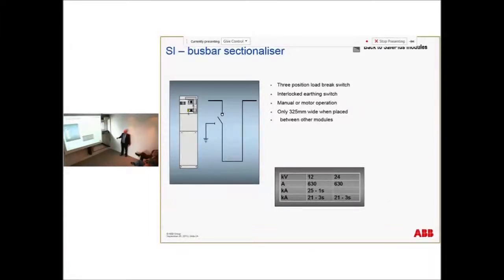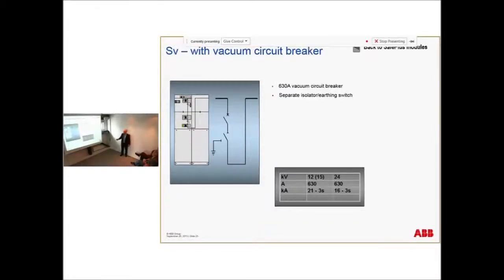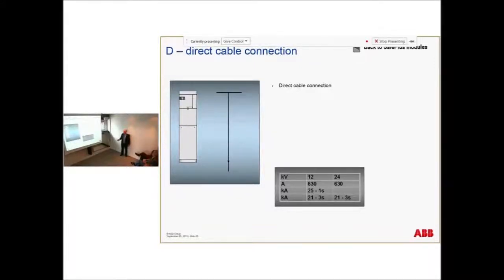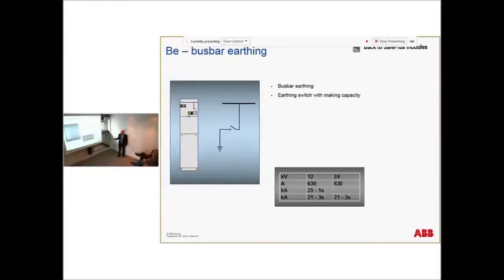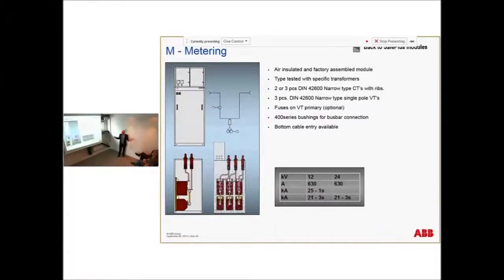Yeah, and then I go quickly through the others. You can disconnect the bus bars, and you can do it with the vacuum circuit breaker, and you can have direct cable connections. This one is very much used for wind towers. In order to save cost, they have just a direct connection and a fused or a vacuum circuit breaker. They are not so concerned about connecting the whole ring, just connecting each single windmill to the grid. And these are all the basic building Lego blocks.